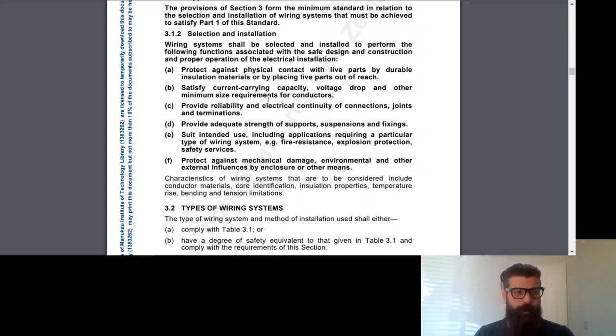So depending on the usage and the location and all of that kind of stuff, what wiring do I need to use? We have it here: protection against physical contact with live parts by durable insulation materials or placing live parts out of reach, satisfying the current carrying capacity, voltage drop and other minimum size requirements for conductors, and so forth. So this tells us all of the things that we need to take into account when selecting what cables we're going to use and then how we make that determination.